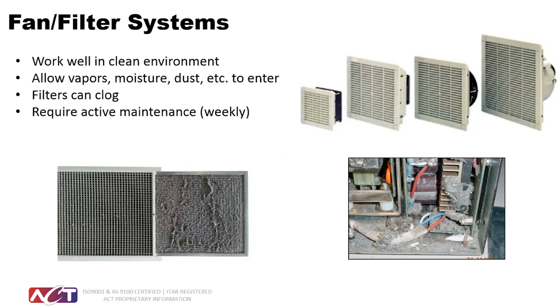Filter fan systems are simple and fairly easy to install, and they work well in clean environments. They do require some maintenance attention as the filters need to be changed regularly. Even with filters in place, some moisture and particulates are still able to enter the enclosure, which limits the NEMA rating of an enclosure that uses this type of cooling approach.